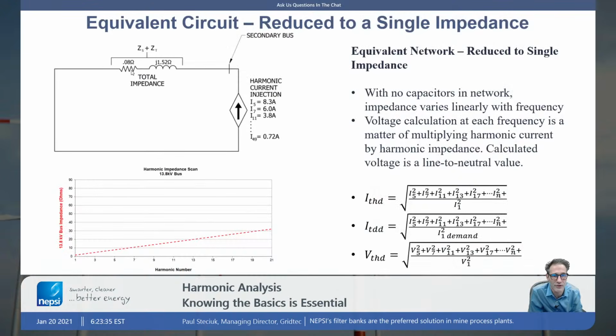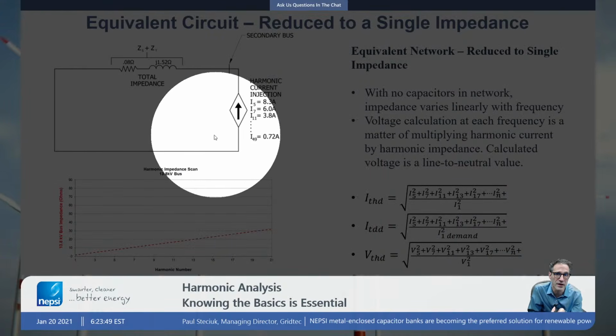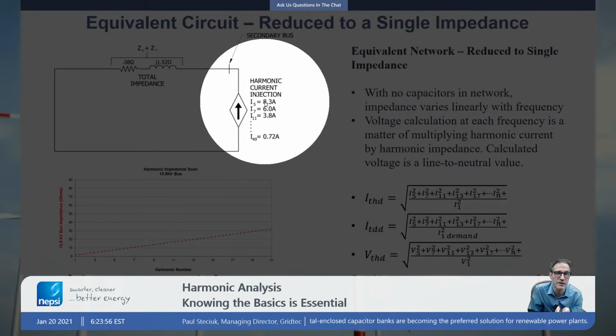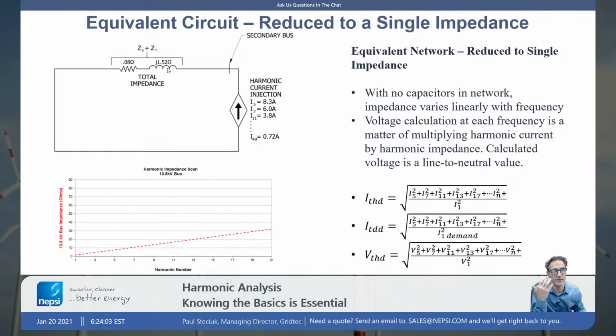The first thing that's interesting to note is that the resistance is very low. It's only 0.08 ohms. So you could more or less throw that out of the analysis for the back of the envelope calculation. We will be just left with a single impedance. And obviously it's easy to calculate the voltage here. If I have the 8.3 amps of fifth harmonic current here, I could take that 8.3 amps, multiply times 1.52 ohms, okay? And again, I've got to multiply it by 5 there because it's the fifth harmonic.